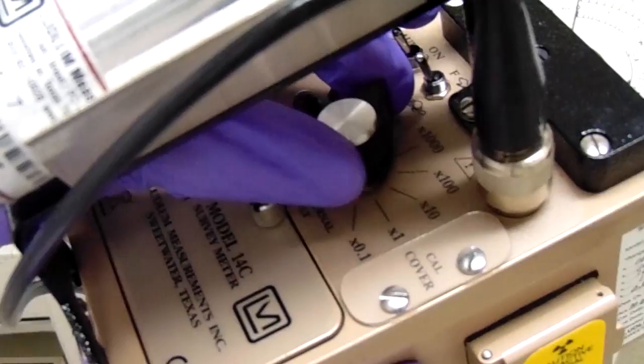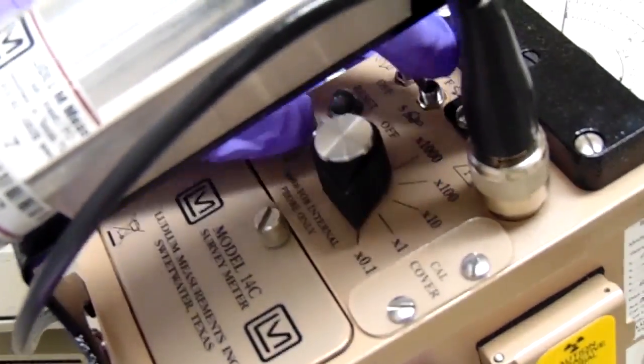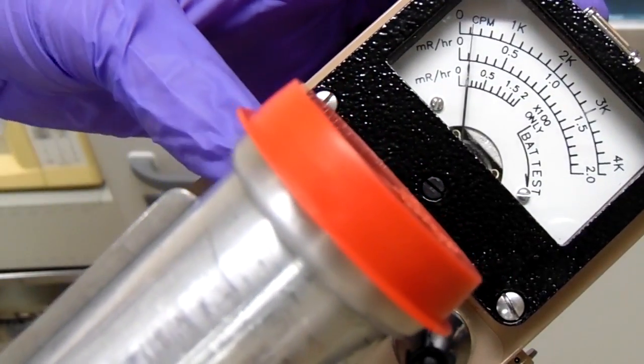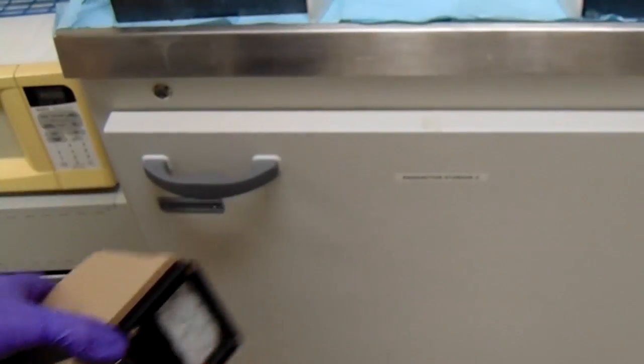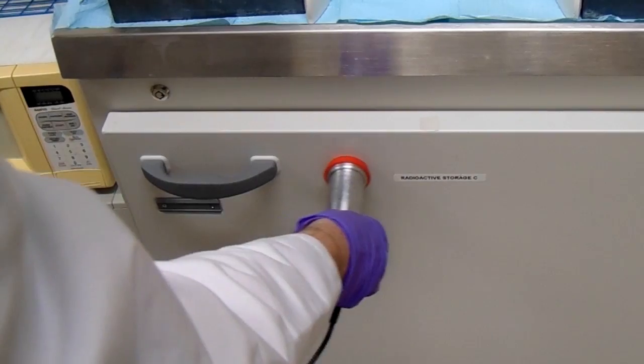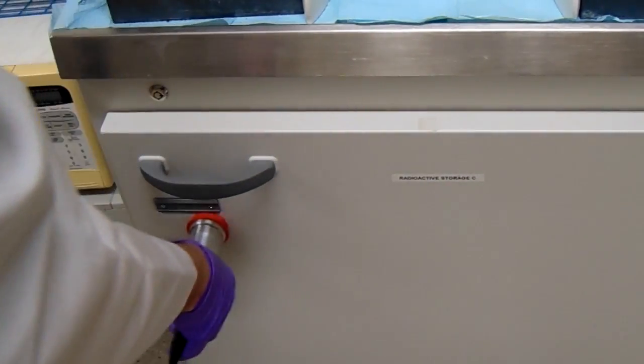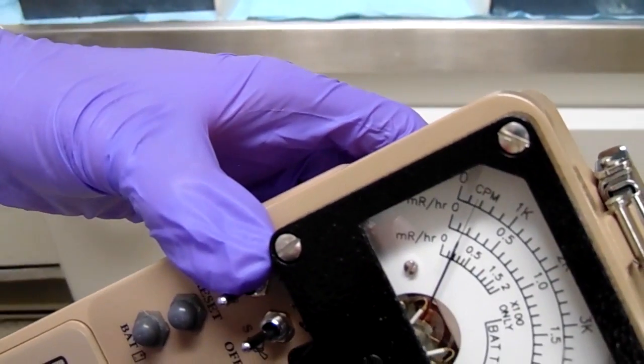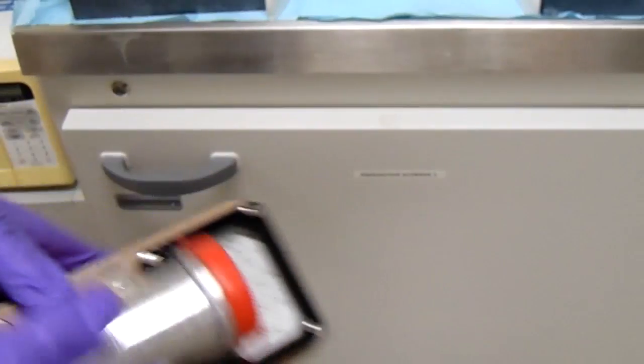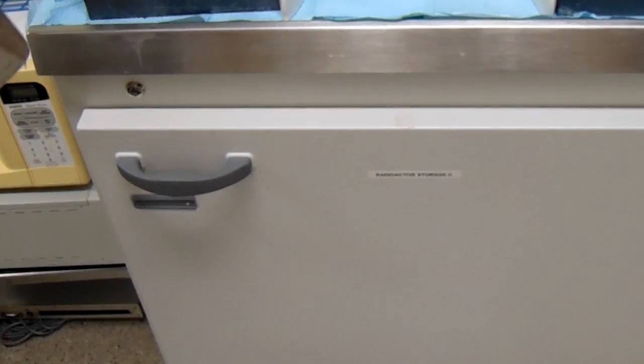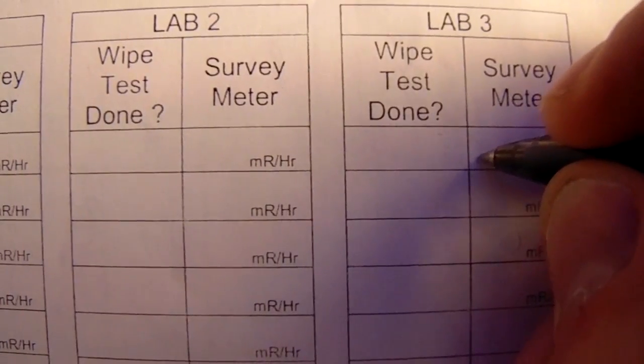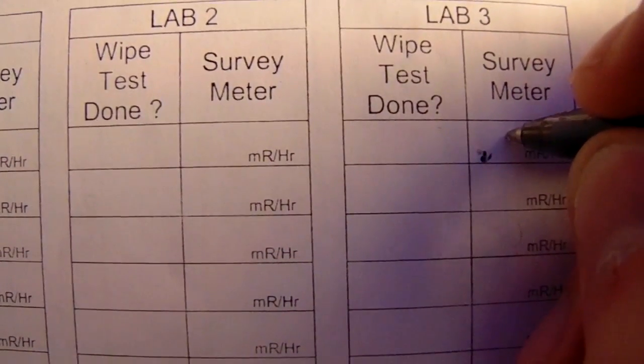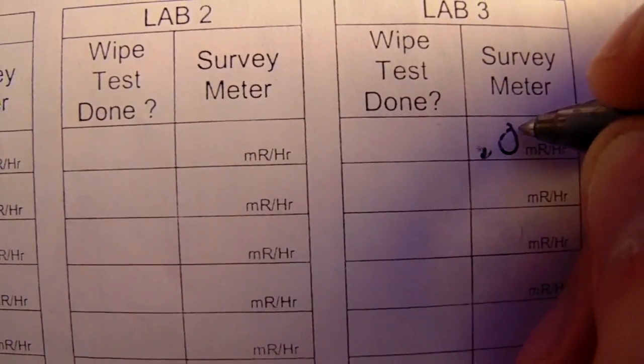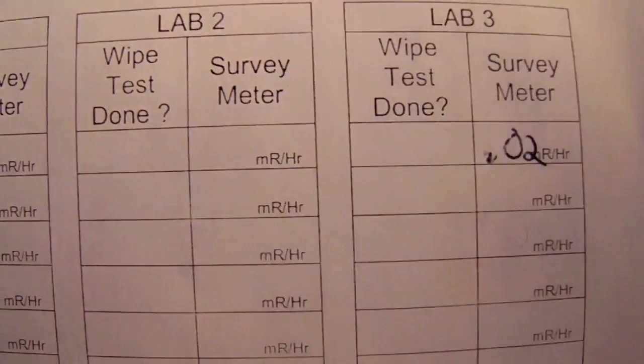We're going to take the survey meter and move it all the way down to the times 0.1 knob. Hit reset and test the battery, and take the probe and put it right up against anywhere where you've handled radioactivity. Take that reading and mark it in your survey and wipe log. Note that if the printer on the well counter is working, you don't need to record each individual wipe count. You can simply just print it out and put it in the binder with the survey sheet.